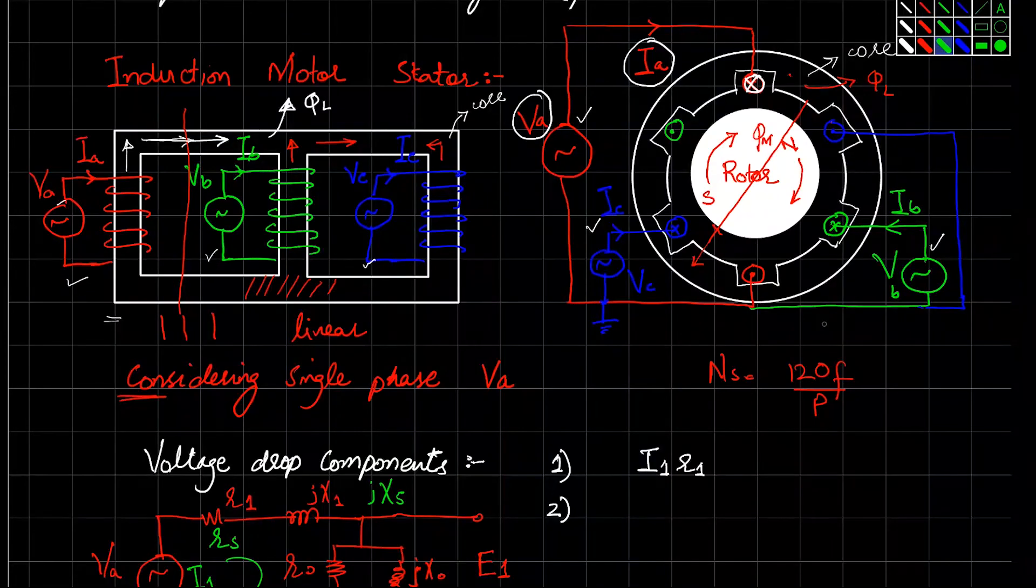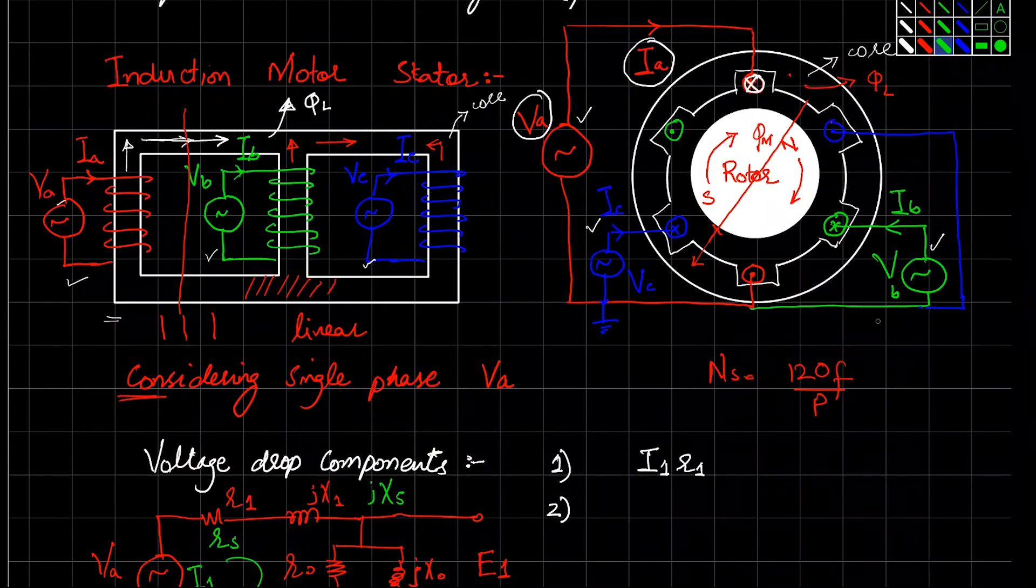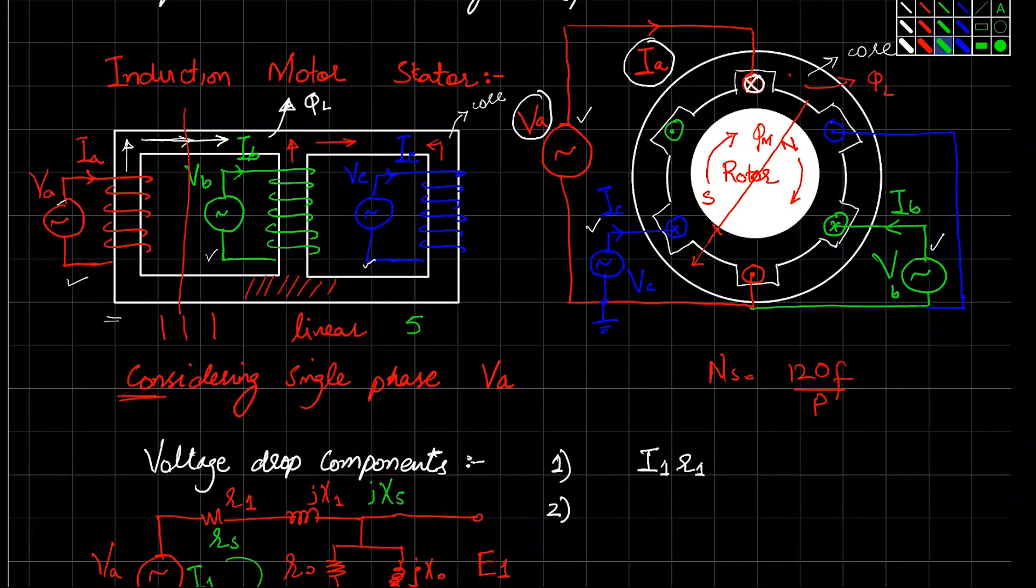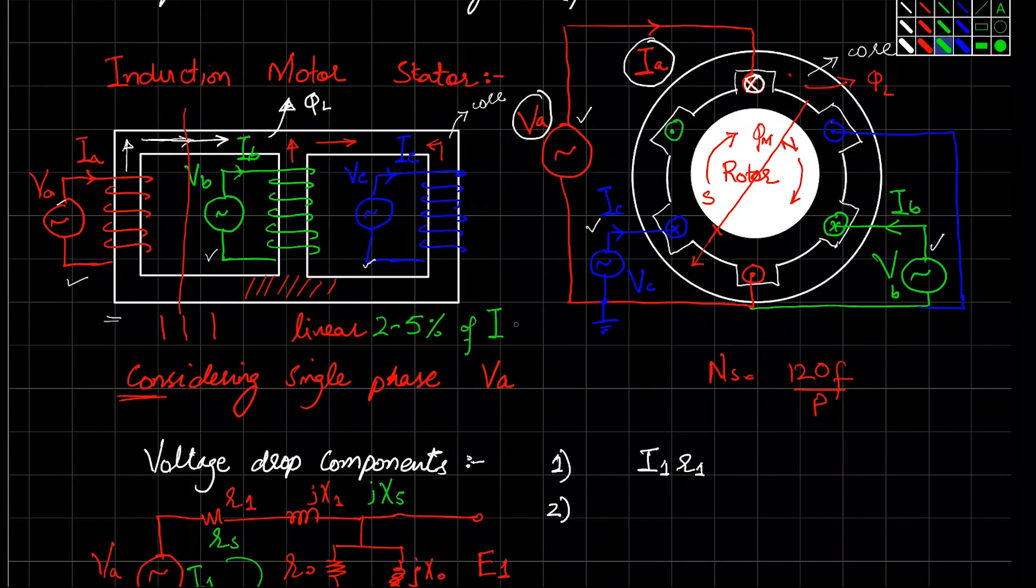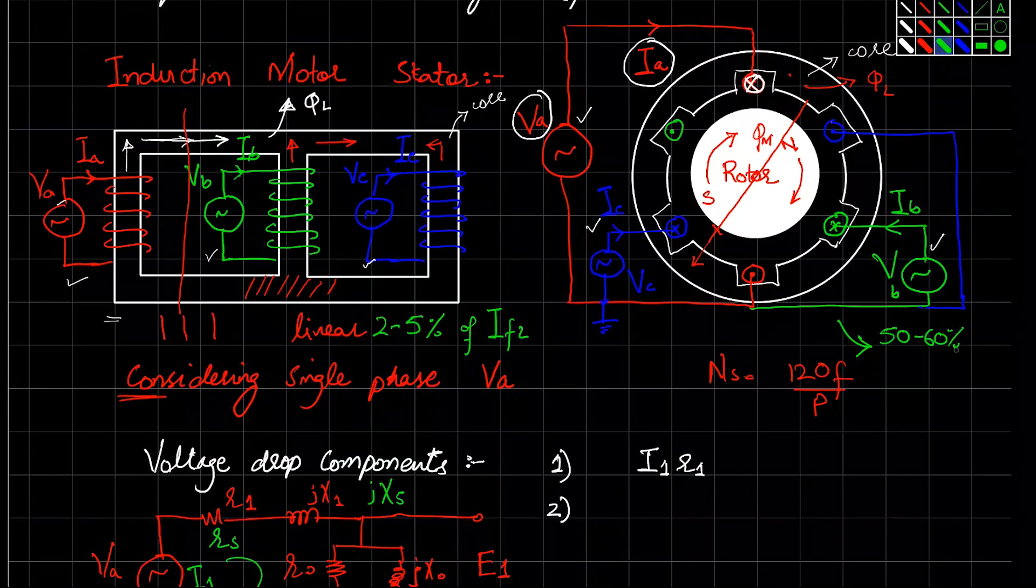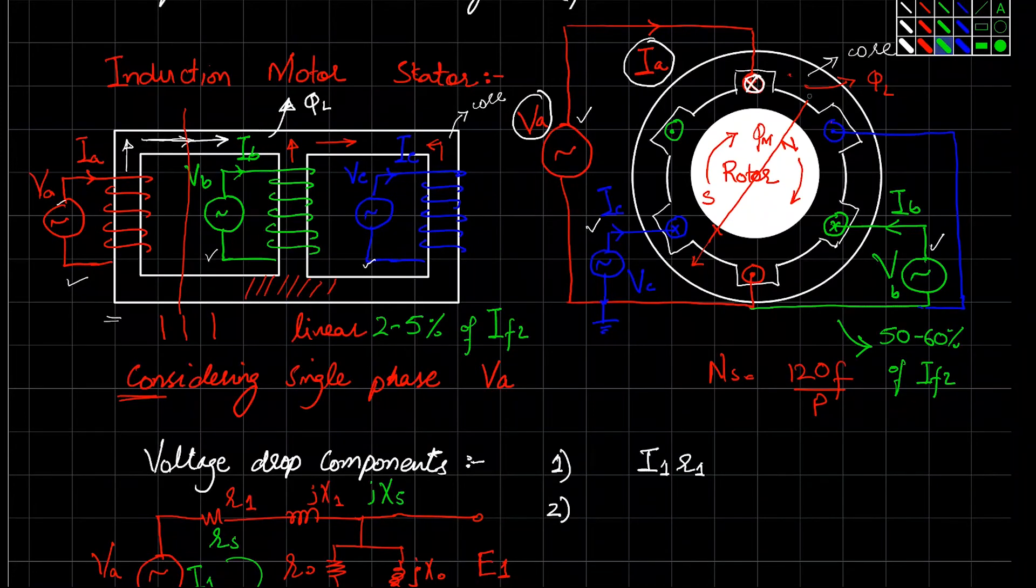The no-load current of transformer is only 2 to 5 percent of full load current, whereas in induction motor you have 50 to 60 percent of the full load current.